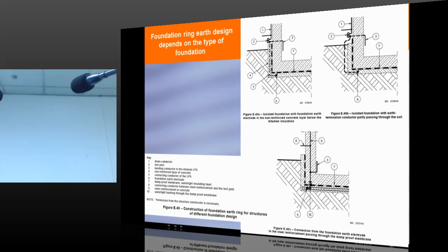Foundation earth design depends on the type of foundation. What is explained is, see this, an isolated foundation with the foundation earth electrode in a non-reinforced concrete layer below the bitumen insulation. This is also from the standard. You see this black and white, the point number 1, it is the down conductor. I think there is some mistake. It is not point number 1, it is 7. Damp proof membrane, watertight insulating layer. So from here I thought it was number 1, no, this is number 7.